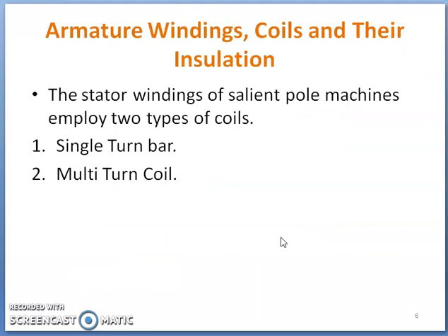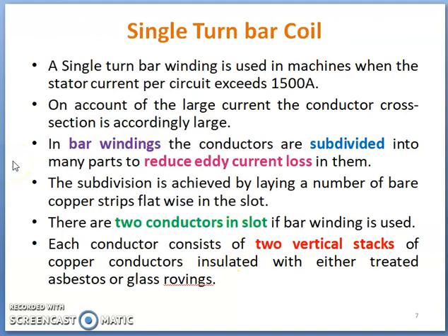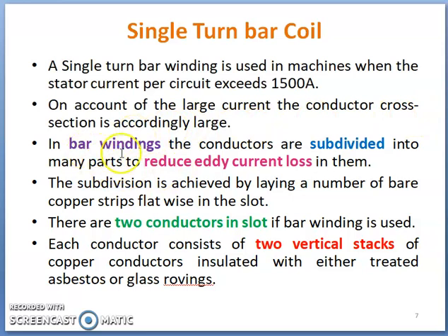Usually in case of a salient pole machine, the stator winding is employed using two types of coil: one is single turn coil and another is multi-turn coil. Single turn bar winding is used in machines when the stator current per circuit exceeds 1500 ampere. For large capacity machines, depending upon output rating, when current is very high, either single turn bar coil or multi-turn coils are used. On account of large current, the conductor cross-sectional area is also very large.